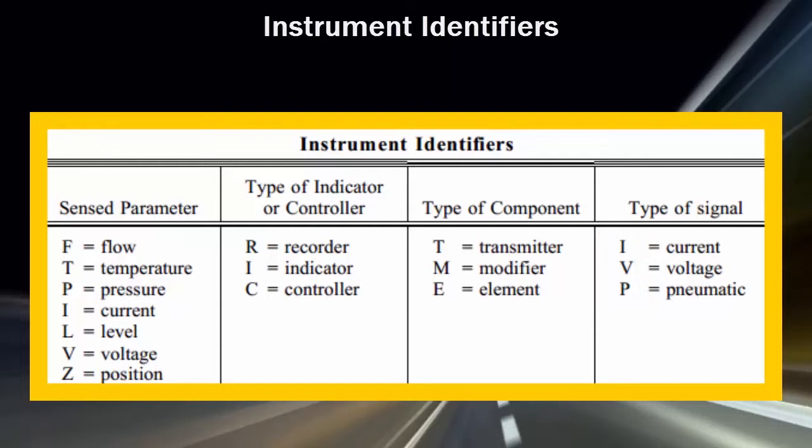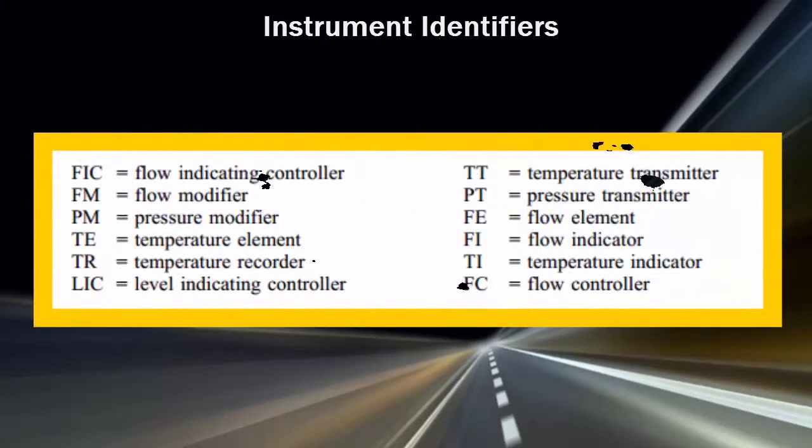The first three columns are combined so that the resulting instrument identifier indicates its sensed parameter, the function of the instrument, and the type of instrument. The fourth column is used only in the case of an instrument modifier and is used to indicate the types of signals being modified. Here is a list of example instrument modifiers.